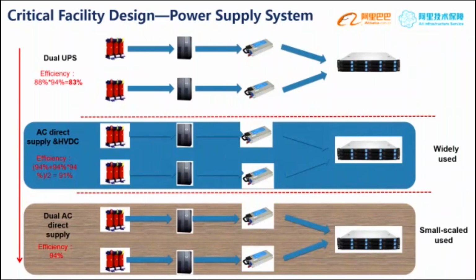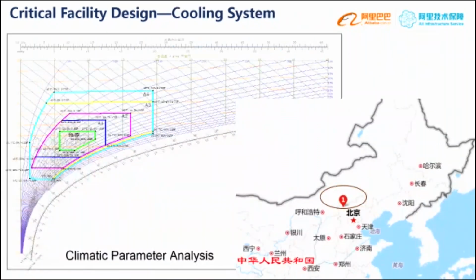The improvement of the power supply system is a good way to lower PUE. So we can imagine if we can eliminate the UPS, or use high voltage DC in our system, the PUE could be lower. In the Zhangbei Data Center, we have deployed several IT modules with BBUs to back up the system, which diminishes power consumption directly. That's another application we will research in our future data centers.